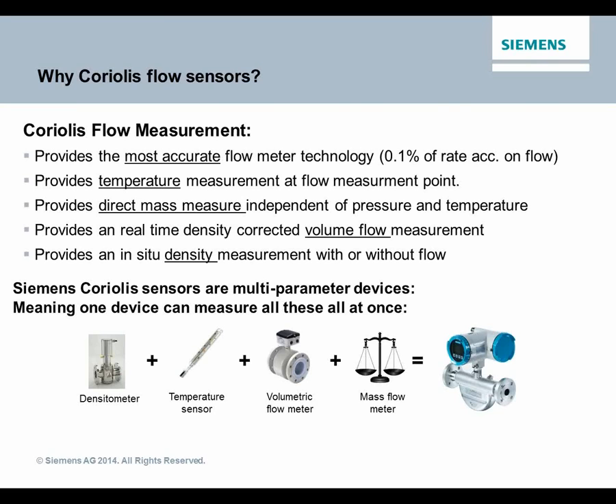Coriolis technology also offers the ability to measure temperature. And the reason they do that is the temperature range on these Coriolis devices can be quite extensive. Some go down as low as -100, -150 degrees Fahrenheit. Some go as high as, specialty meters of course, go as high as 400 degrees, 500, 600, 700 degrees Fahrenheit. So the temperature has a significant effect on how the Coriolis tube vibrates. And because of that, they need to monitor temperature quite closely.